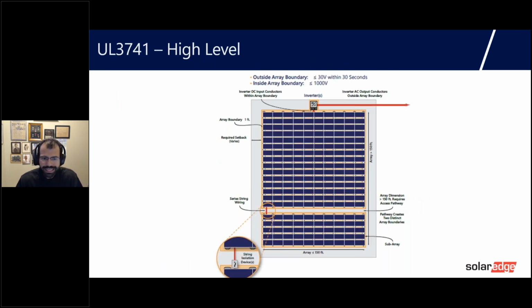Okay. The introduction of the UL 3741 standard for photovoltaic hazard control in 2020 was hailed as an important milestone in the solar industry's continuing drive to improve solar system safety. Building on rapid shutdown best practice first introduced in the 2014 code, it was conceived to equip the solar industry with more options to accomplish rapid shutdown compliance in PV arrays, with the primary objective being to protect firefighters when dealing with fires in buildings with solar installations. In this respect, UL 3741 has achieved a notable success. However, concerns are arising regarding the safety of some of the PV hazard control solutions that have entered the market since the regulation's introduction.